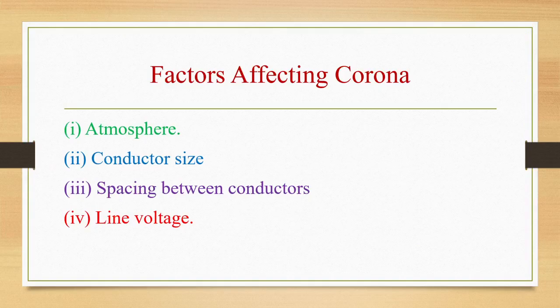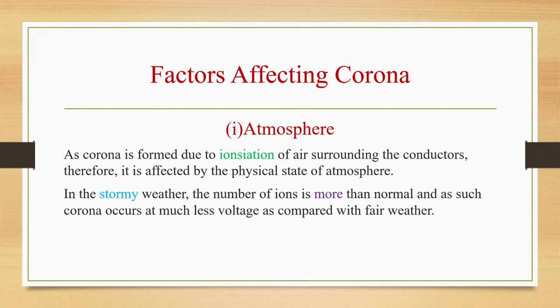Let us see what are the factors affecting corona. There are 4 factors which are affecting the corona. First is atmosphere. Second is conductor size. Third is spacing between conductors. Fourth is line voltage. Let us see the first one, atmosphere. As corona is formed due to ionization of air surrounding the conductors, it is affected by the physical state of atmosphere. In stormy weather, the number of ions is more than the normal and as such corona occurs at much less voltage as compared with fair weather.